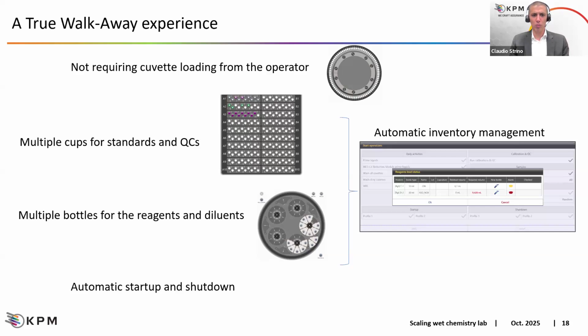And moreover, we can also automatize the startup and the shutdown procedures. So what does it mean? We can program the automatic startup before our arrival in the lab. So when we arrive, the instrument is ready to start analysis. We don't need to wait for any starting time, because everything has already been done, and we can also program automatic shutdown procedures. For those parameters that are not sensitive to onboard timing, we can also, in the automatic startup program, run calibrations and QCs automatically to check if the calibrations are okay or not.